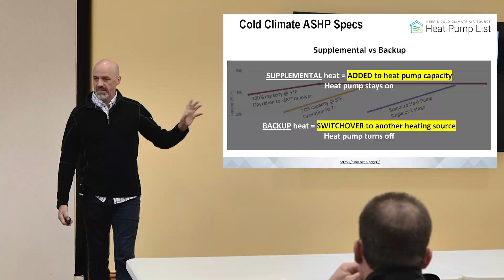Cold climate air source heat pump specs—we're going to spend some time in this arena. The top chart is 100% capacity at 5 degrees, that red line we saw. That red line across the top is the capacity of the heat pump represented in that chart.